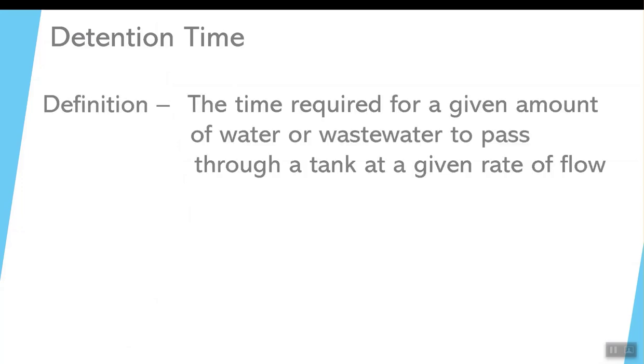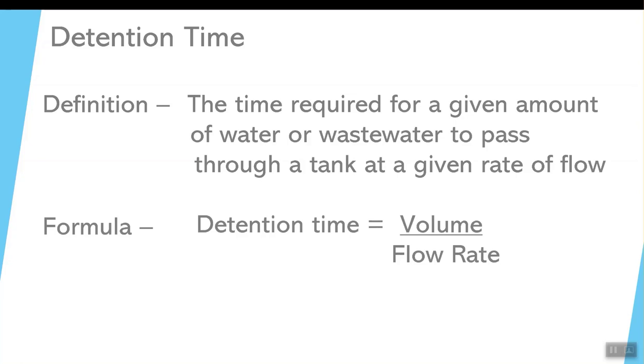Detention time, when we're talking about detention time, it's a term that some people don't catch on to. But the basic definition is the time required for a certain amount of water to enter or leave a tank at a given rate of flow. The formula for it is detention time equals the volume of the tank divided by the flow rate.